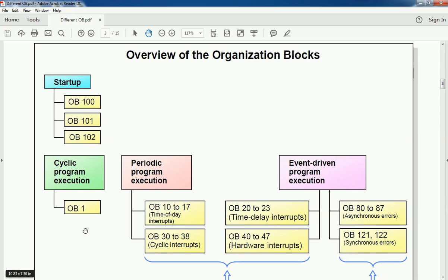Next is cyclic program execution: main OB1 which executes periodically. The logic developed in the main OB will execute cyclically. Then we have periodic program execution — OB10 to OB17 are time-of-day interrupts, and OB30 to OB38 are cyclic interrupt OBs. Next, event-driven program execution OBs include time delay interrupts, hardware interrupts, asynchronous errors, and synchronous errors.